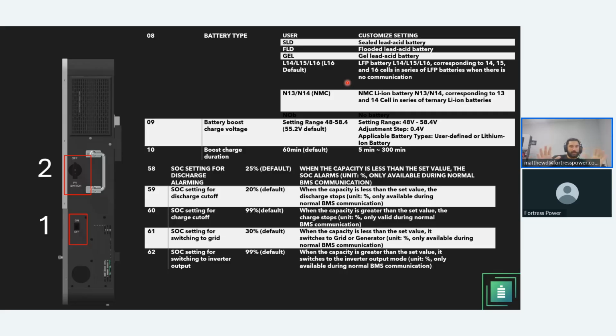But all of these, they come by default. The eBoost comes by default SBU, which is self-consumption mode. It's basically going to prioritize the PV to your loads and battery charging. And then when your battery is not sufficient, when SOC depletes, it's going to resort to either generator or to the grid, right? Whichever is available. If grid is available, then the generator is not going to turn on. If grid is not available, then the generator will turn on. And that's going to be on parameter 61, as I mentioned.